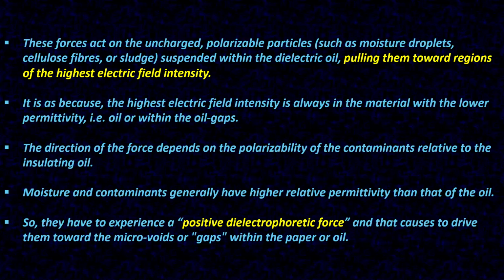The direction of the force depends on the polarizability of the contaminants relative to the insulating oil. Moisture and contaminants generally have higher relative permittivity than that of the oil. So, they experience positive dielectrophoretic force, and that drives them toward the microvoids or gaps within the paper or oil.